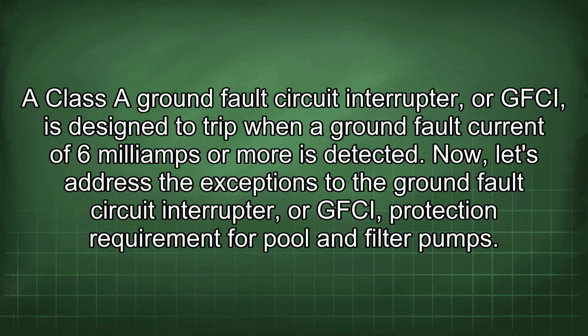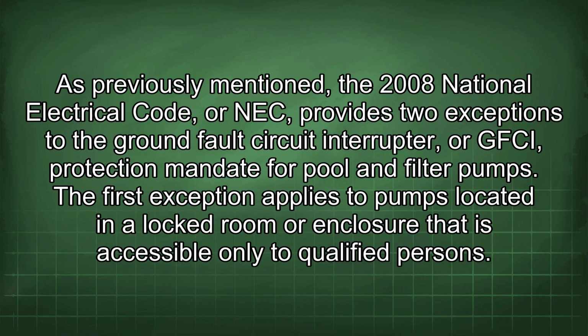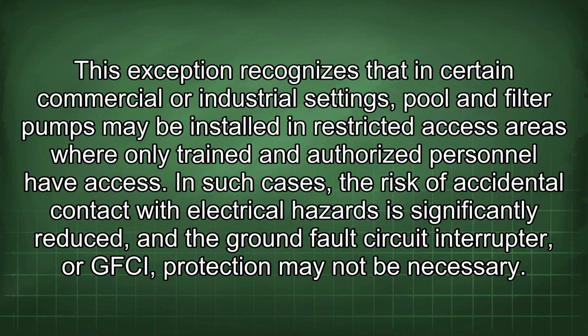Now, let's address the exceptions to the GFCI protection requirement for pool and filter pumps. As previously mentioned, the 2008 National Electrical Code, or NEC, provides two exceptions to the GFCI protection mandate for pool and filter pumps. The first exception applies to pumps located in a locked room or enclosure that is accessible only to qualified persons. This exception recognizes that in certain commercial or industrial settings, pool and filter pumps may be installed in restricted access areas where only trained and authorized personnel have access.